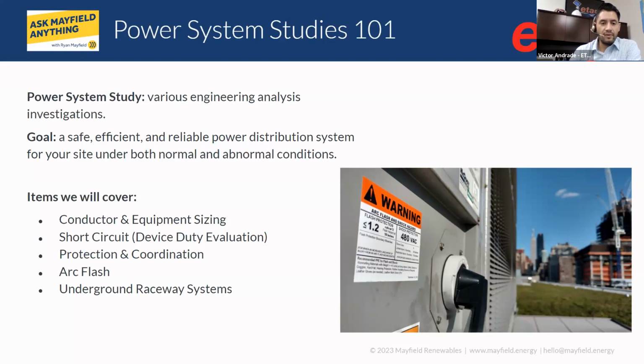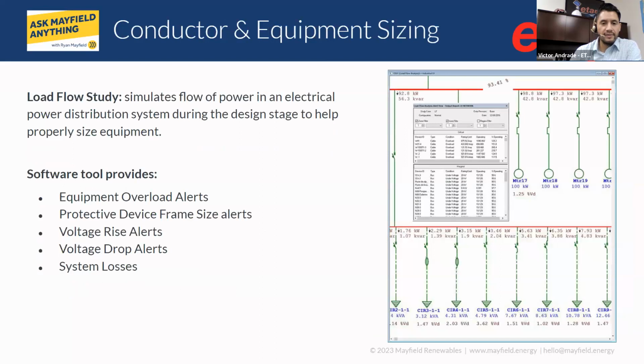All right, great. Let's start talking about the conductor and equipment sizing. The conductor and equipment sizing is actually part of the load flow analysis, or a load flow study. What it does is it simulates the power flow of an electrical system while you're doing the design stage. And this is so important because it helps us size equipment such as transformers, cables, inverters, and very importantly, conductors. Depending on the length and the load on the other side of the feeder, we want to make sure that we're sizing the conductors properly. So those are basic tools provided by the software.